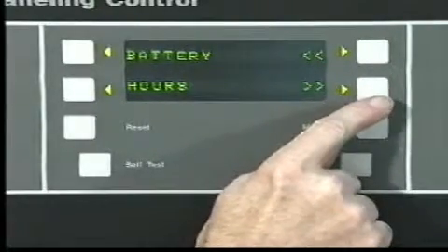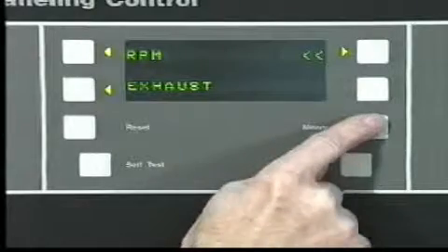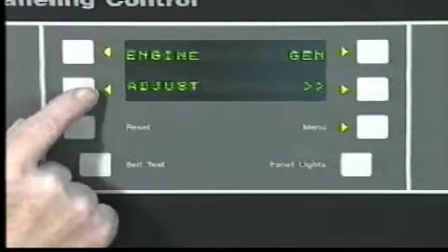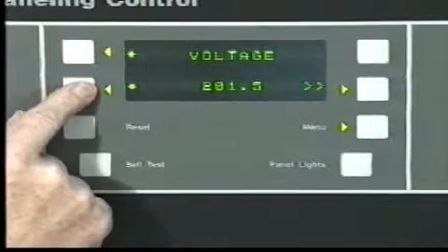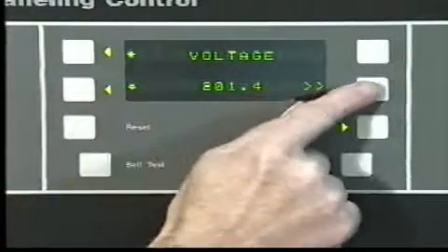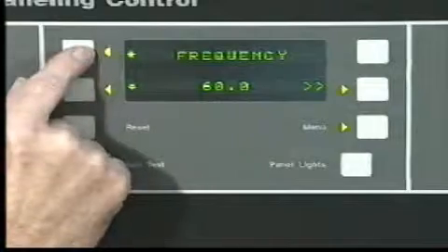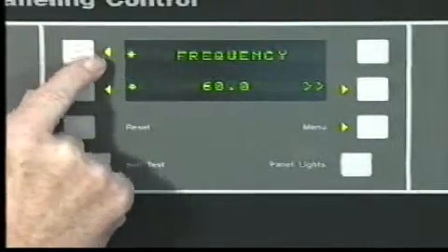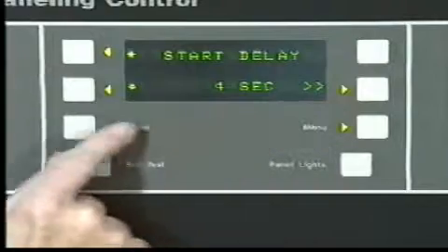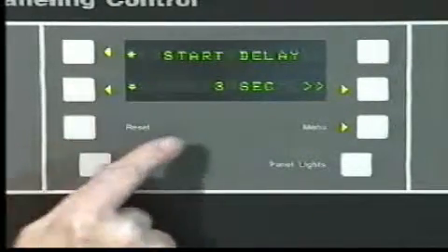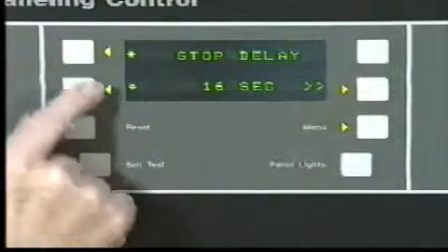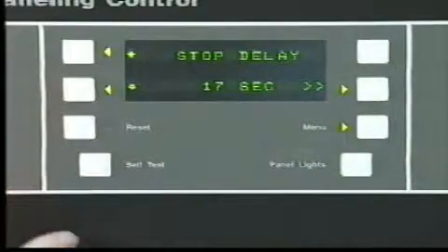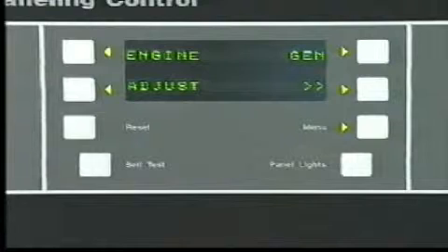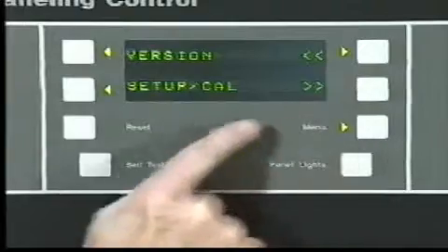The same idea applies to checking the generating data. From here, you can make minor adjustments to the voltage, to the frequency, to start-up time, and to cool-down time. These adjustments are limited to prevent misadjustment and possible equipment damage. Power command control is smart, allowing access for larger adjustments only by way of authorized operators using a security code.